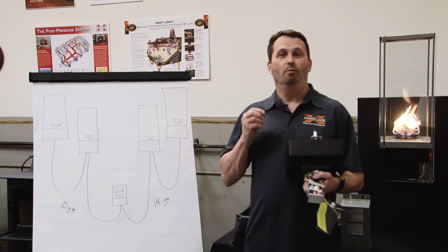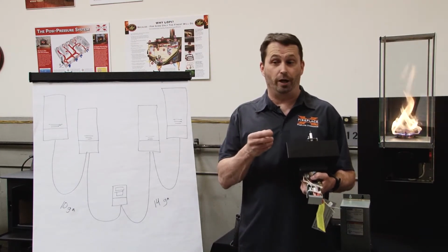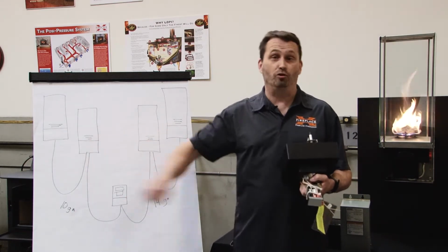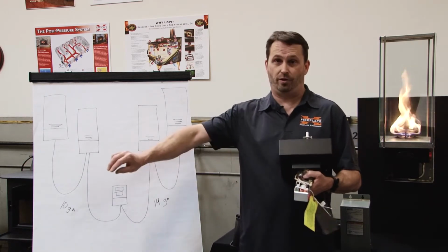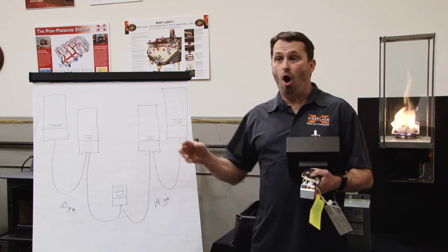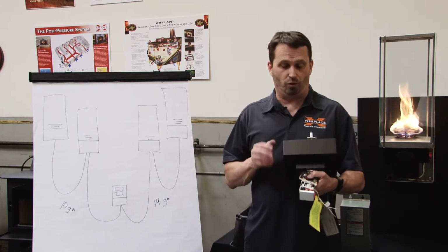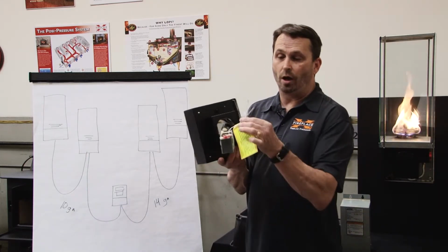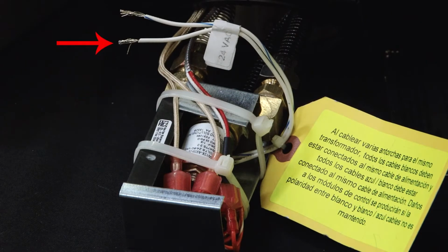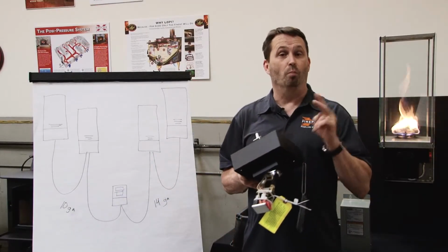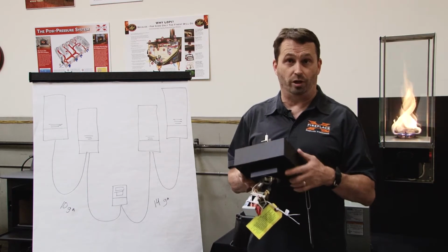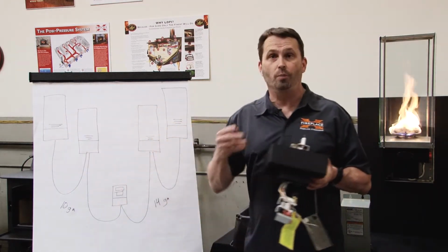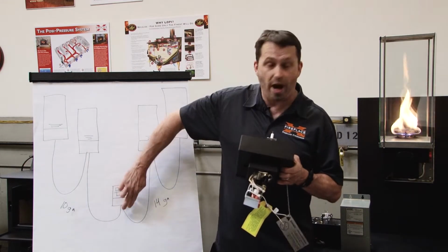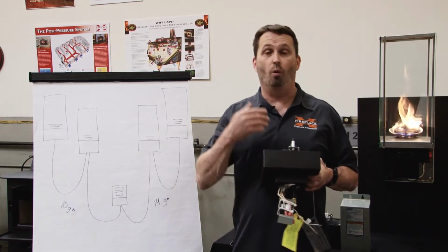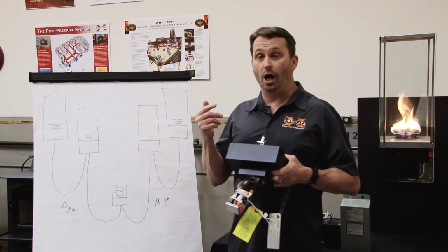All right, lastly, number 3, polarity of the torch. When we say polarity, we refer to the power to the torch and then the return of the power from the torch back to the transformer. So the polarity is all the power to the torches has to be aligned from torch to torch. On the power input wires to the torch, we have a white wire and a white blue wire. The white blue wires must never come in contact with a white wire when you're doing multiple torches on a transformer installation. If you just have one torch on the transformer, the connection of the power wires to the transformer doesn't matter. But as soon as you go with more than one torch on your installation with your transformer, the polarity comes into play.